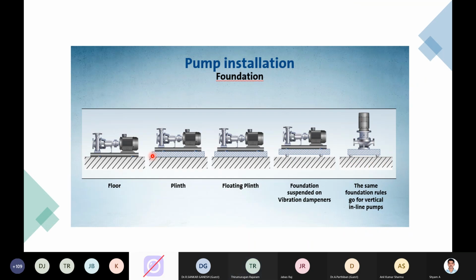And some more efficient way of operating pumps is mounting the pump properly on the floor. There are different design criteria for different situations, from a normal floor mounting to a plinth. The recommended one would be the plinth, with a proper foundation and bolts arresting the pump movement in any direction. And where there are situations with excess vibrations penetrating from instruments or machines very nearby the pumps, you have vibration isolation dampeners or vibration isolators, which can still safeguard the pump from excess vibration from the nearby machines.